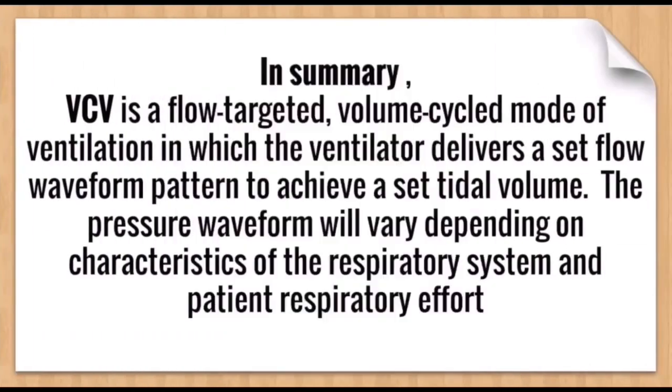Now, in summary, volume control ventilation is a flow targeted, volume cycled mode of ventilation in which the ventilator delivers a set flow waveform pattern to achieve a set tidal volume. So we have set the tidal volume, we have set the flow. The pressure waveform will vary depending upon the characteristics of the respiratory system and the patient's respiratory efforts.